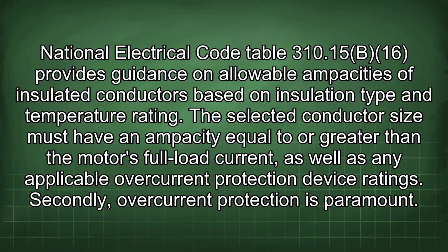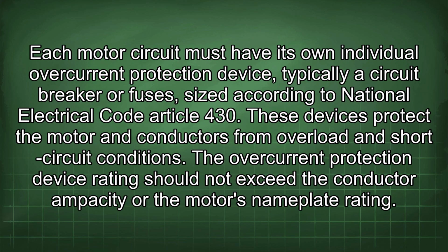Secondly, overcurrent protection is paramount. Each motor circuit must have its own individual overcurrent protection device, typically a circuit breaker or fuses, sized according to National Electrical Code Article 430. These devices protect the motor and conductors from overload and short-circuit conditions. The overcurrent protection device rating should not exceed the conductor ampacity or the motor's nameplate rating.